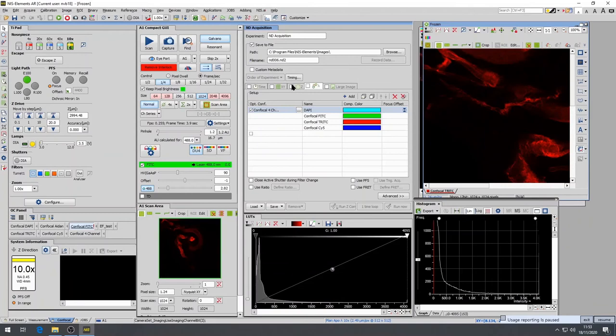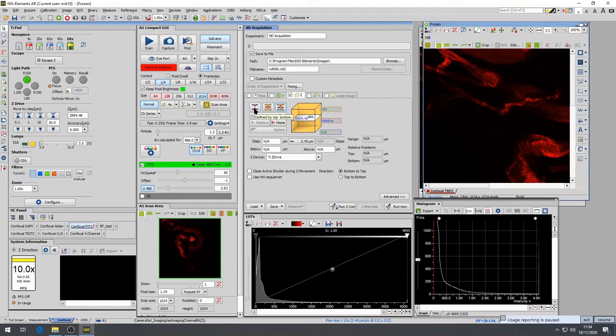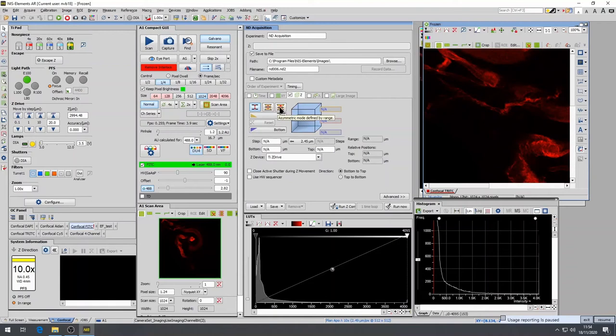Within the ND acquisition box, you are also able to do a Z-Stack. The Z-Stack takes advantage of the confocality of the A1R to acquire a 3D image of your sample. And there are multiple ways to define the parameters of the Z-Stack. You can set your Z-Stack by defining the top and bottom of your sample or a symmetric Z-Stack. And a third option is the asymmetric Z-Stack.